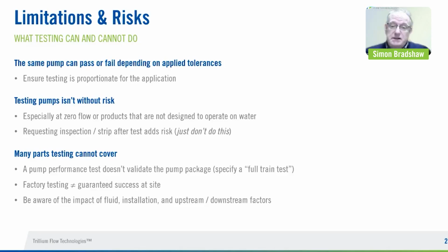Finally, some things that testing doesn't cover. A performance test does not validate the pump package. For that, you would have to specify a full train test. Factory testing does not guarantee success at site. A factory test setup is going to be optimal.